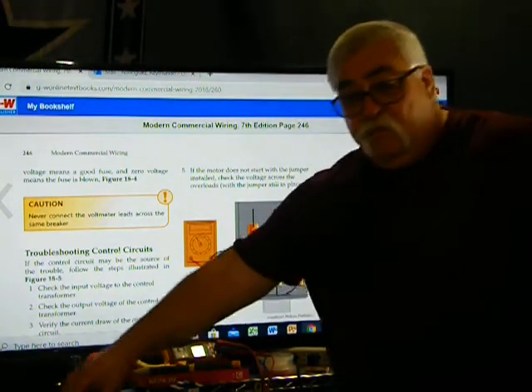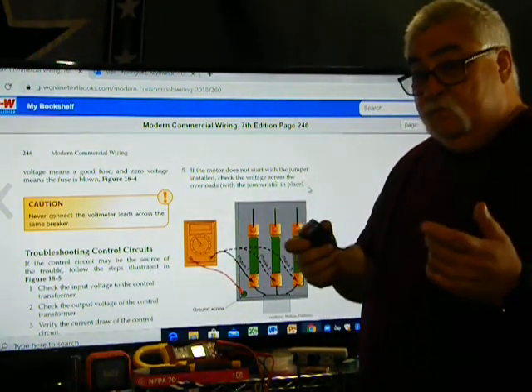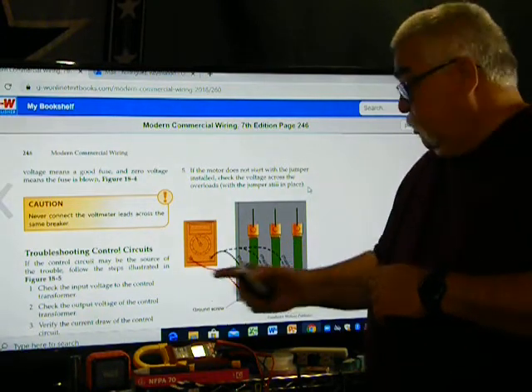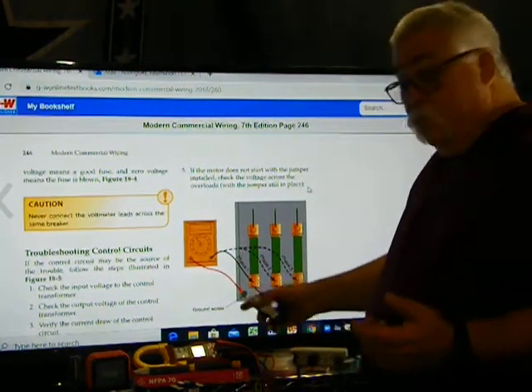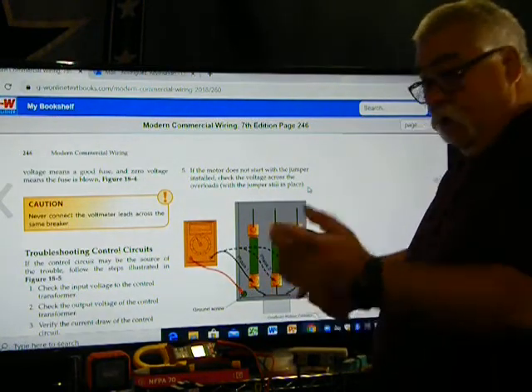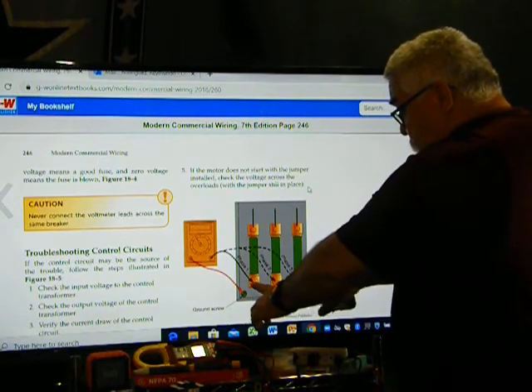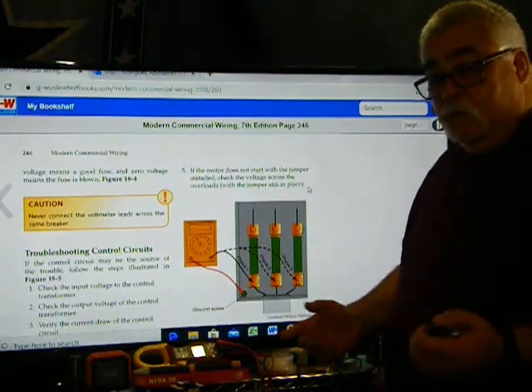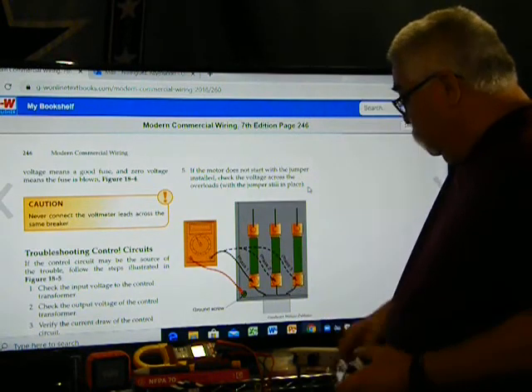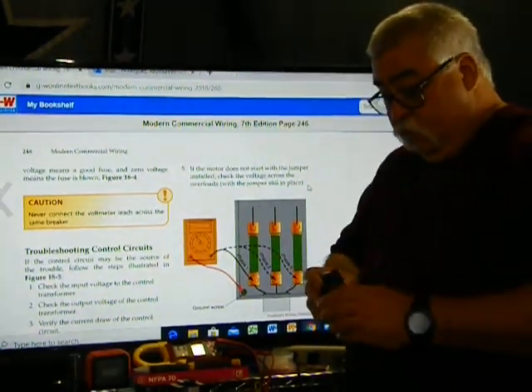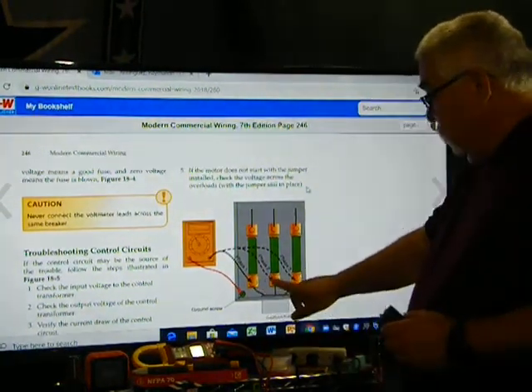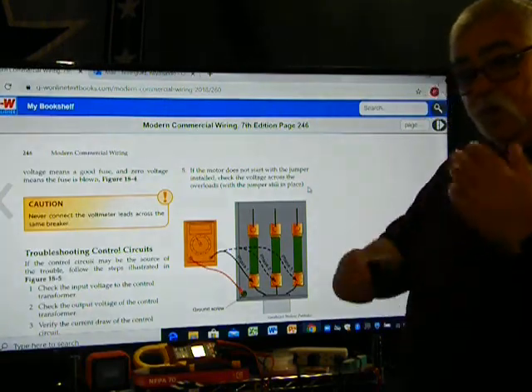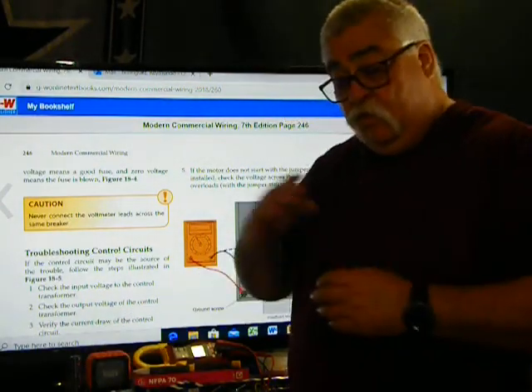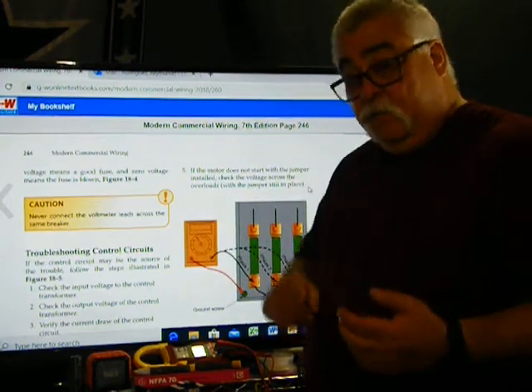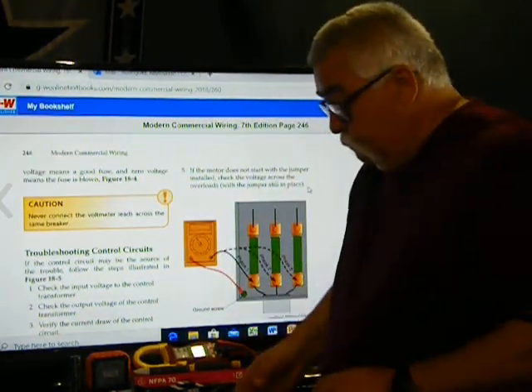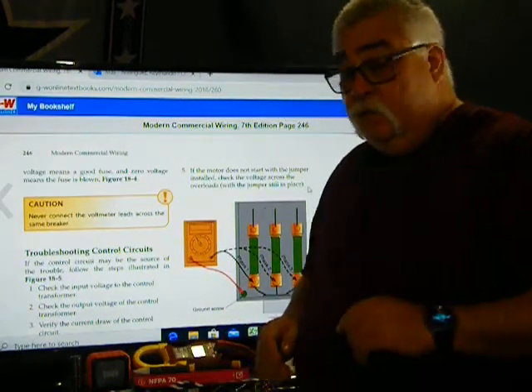If a breaker trips, if your overloads trip, why did the overloads trip? They shouldn't. Why did they trip? Okay, first step is there's a problem within the windings of the motor. Is it going to ground or is it going to hot? And then you just go hot to hot, hot to hot. Again, just go A to B, A to C, and then it should get a reading. So if you go across each phase, then you're checking across the phases. A to B, A to C, and then B to C. Make sure your windings, the numbers are the same. You should pick up resistance because it's going across the windings. But if that number comes down to 0, then there's a problem.